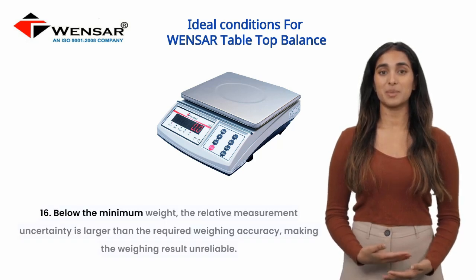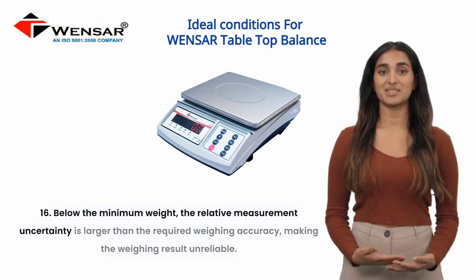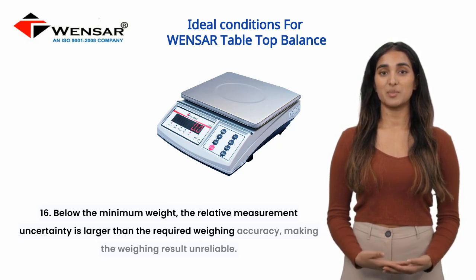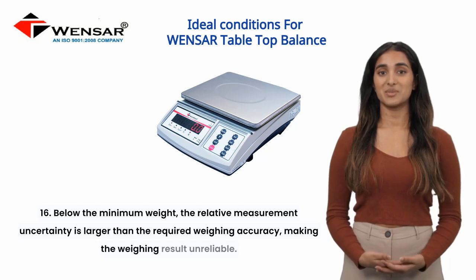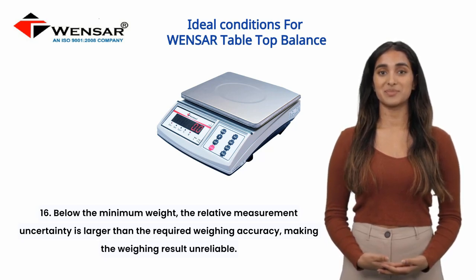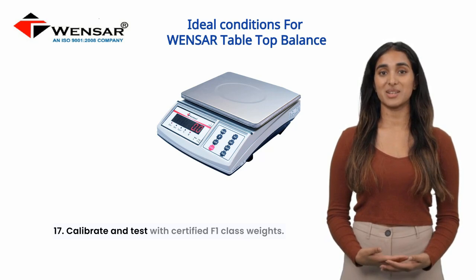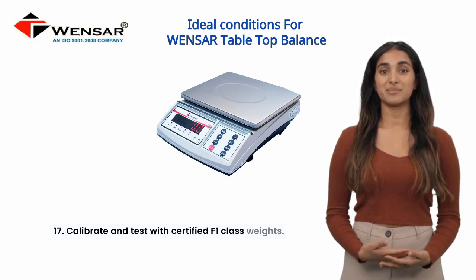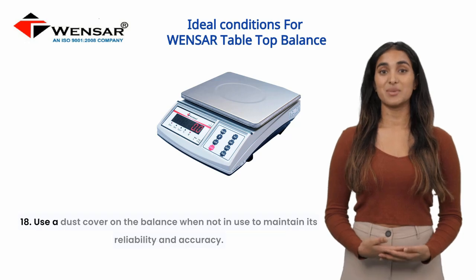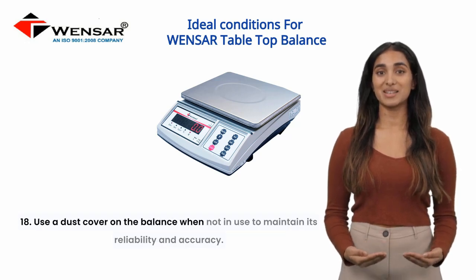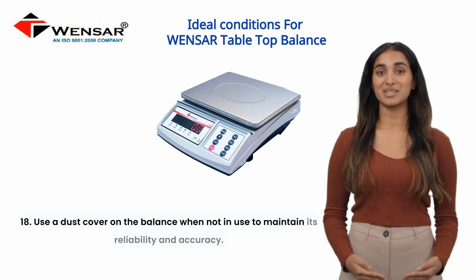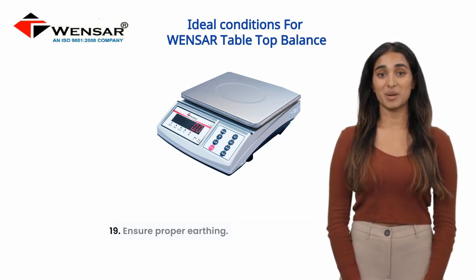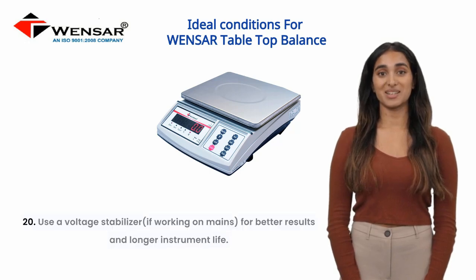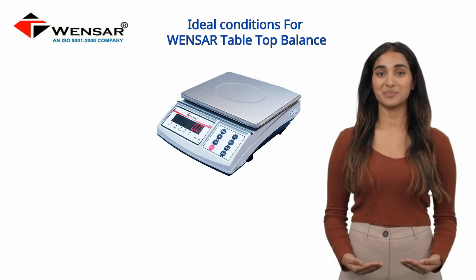16. Below the minimum weight, the relative measurement uncertainty is larger than the required weighing accuracy, making the weighing result unreliable. 17. Calibrate and test with certified F1 class weights. 18. Use a dust cover on the balance when not in use to maintain its reliability and accuracy. 19. Ensure proper earthing. 20. Use a voltage stabilizer, if working on mains, for better results and longer instrument life.